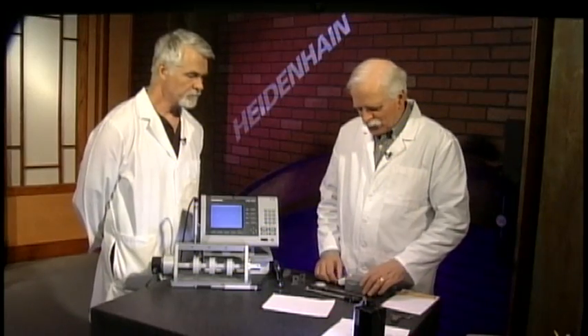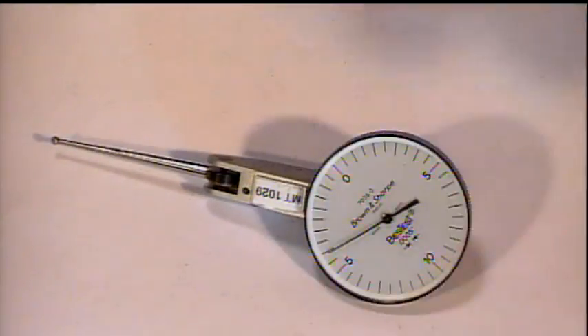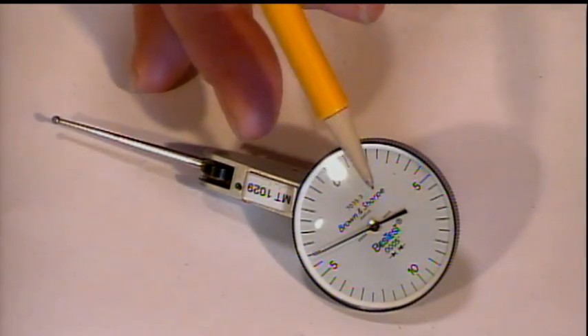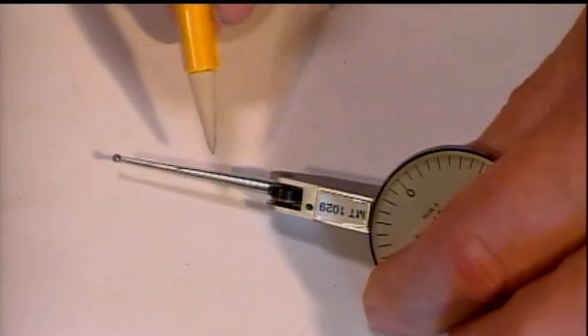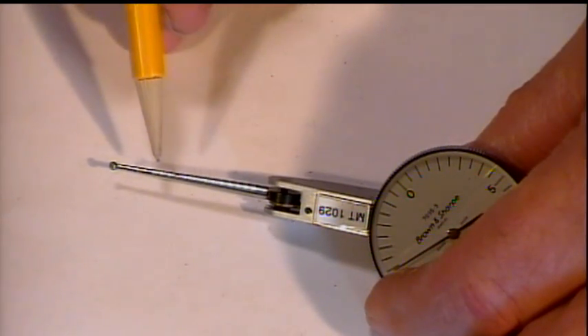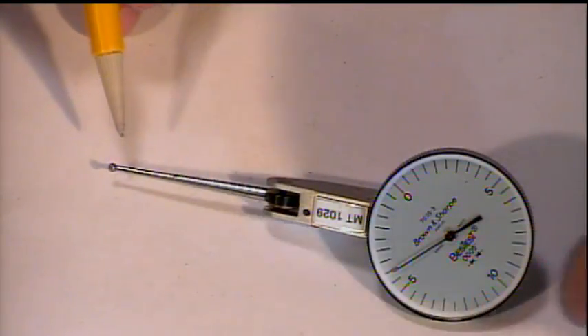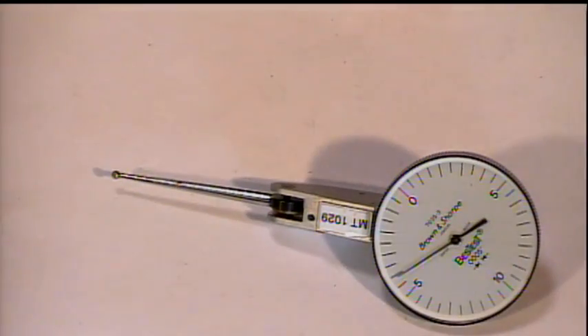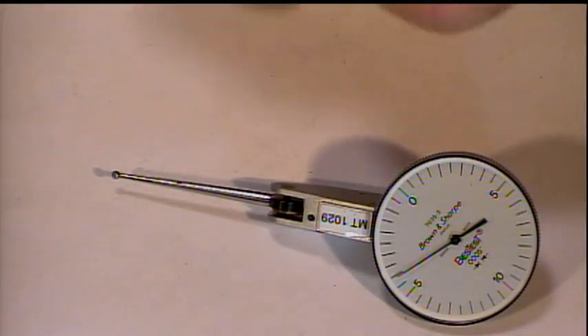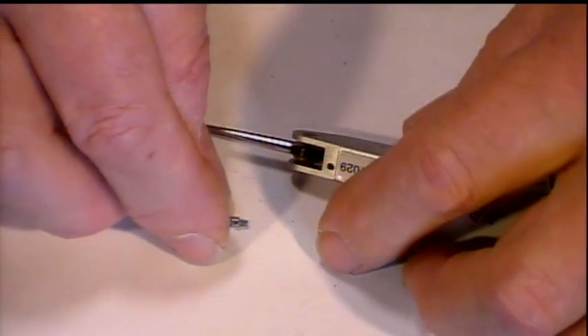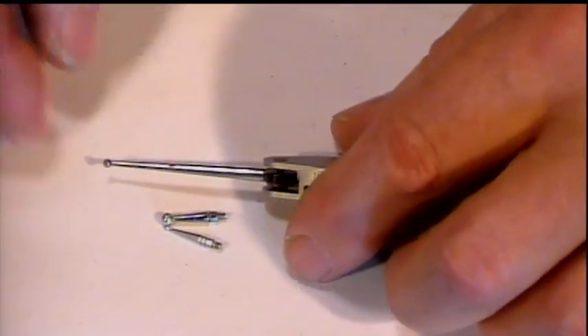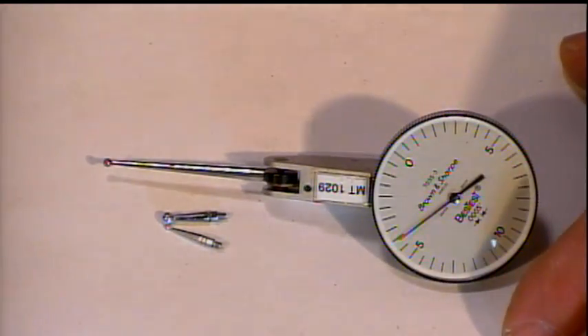So indicators, let's talk a little bit about indicators. Indicators typically have the crystal, and they have the contact point. The contact point is the long arm with the ball on the end of it. All the manufacturers make them in different lengths, and they're not interchangeable as far as length. You could not put the small contact points on this indicator and have it read linear.